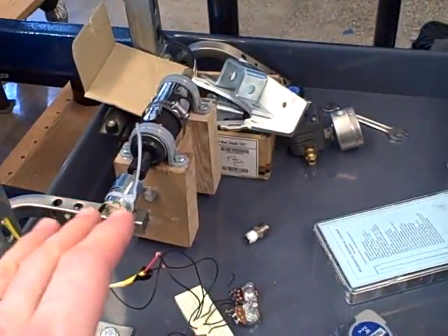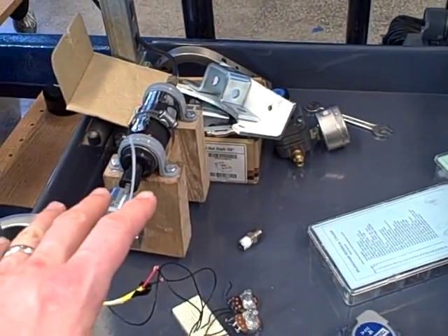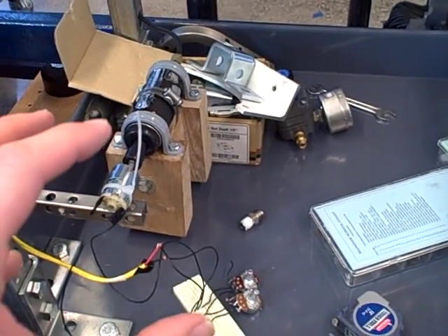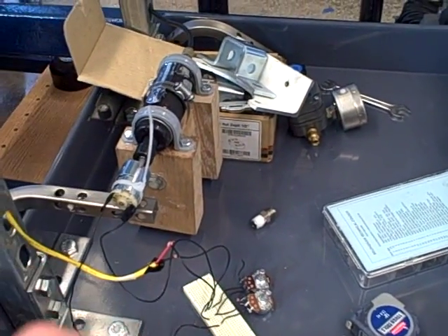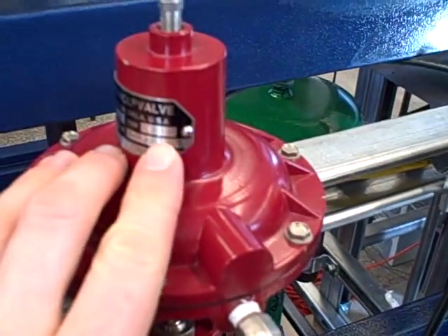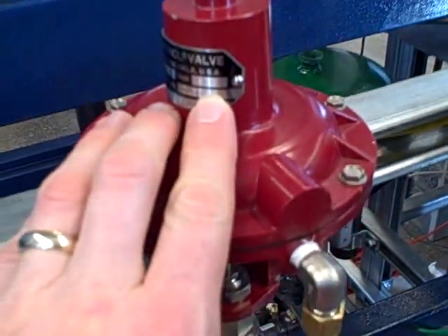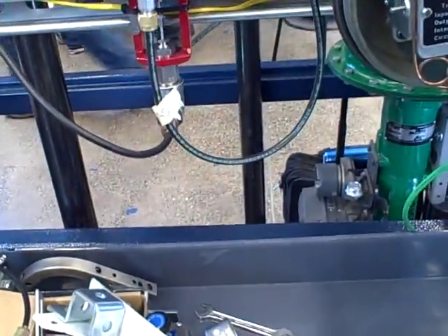This is an example of a process that has a non-linear process gain. Down towards the low end of operation, it's extremely responsive. At the upper end, it's not so much. One of the reasons for that is our control valve here does not have an equal percentage trim. It has a linear trim, which means there's some distortion in its characteristic towards the bottom end of its range.